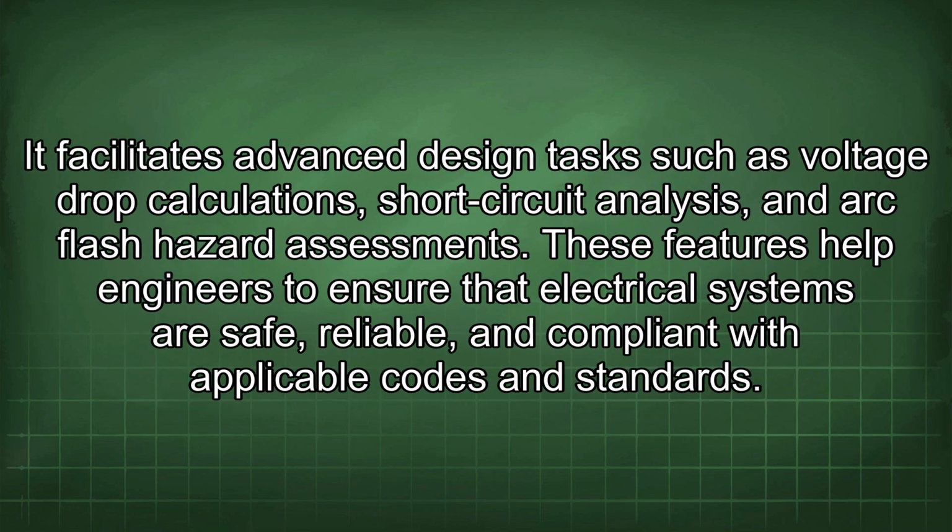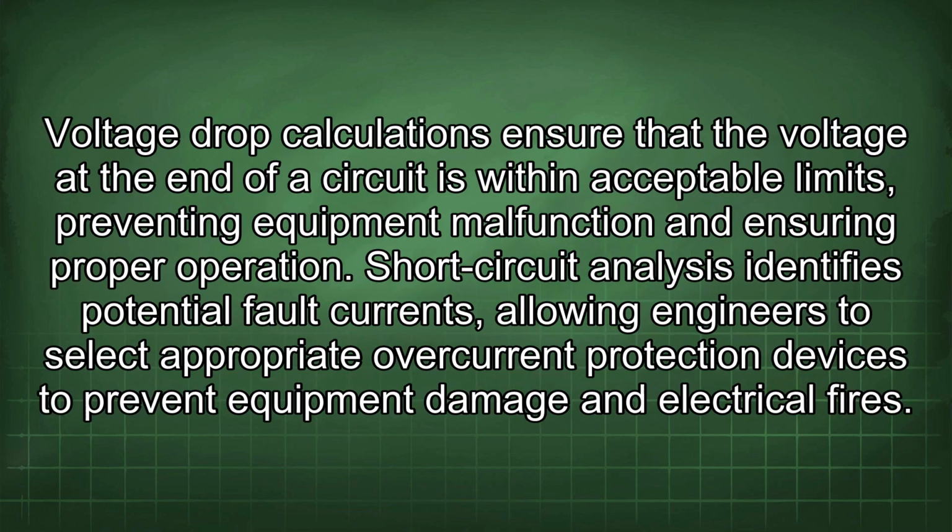It facilitates advanced design tasks such as voltage drop calculations, short-circuit analysis, and arc flash hazard assessments. These features help engineers to ensure that electrical systems are safe, reliable, and compliant with applicable codes and standards. Voltage drop calculations ensure that the voltage at the end of a circuit is within acceptable limits, preventing equipment malfunction and ensuring proper operation. Short-circuit analysis identifies potential fault currents, allowing engineers to select appropriate overcurrent protection devices to prevent equipment damage and electrical fires.